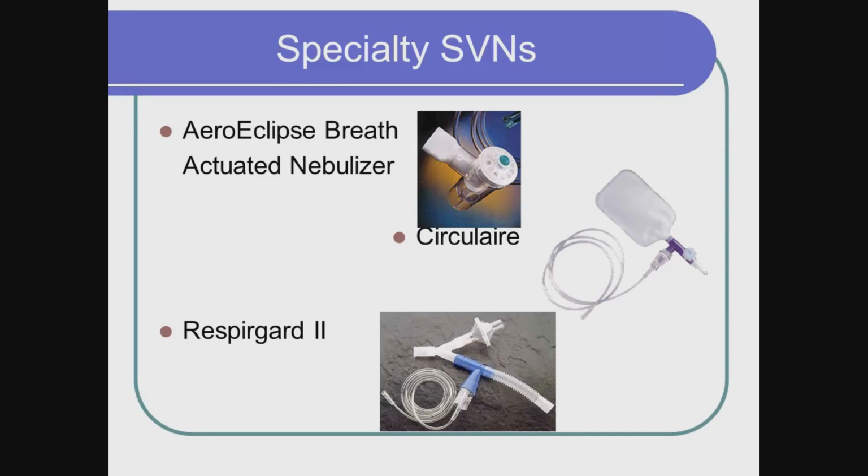it'll be. These are just some of the specialty ones we talked about that are breath activated. The Respirgard II is one that is specifically used for any medication that you don't want their exhaled aerosol to be vented to the atmosphere. We actually have a filter on it so that when they breathe in, they can only breathe in through the nebulizer, but when they breathe back out, it's got a one-way valve that it only can go out through that port and be filtered in the process. Okay.